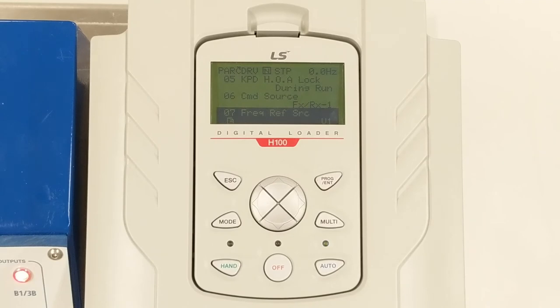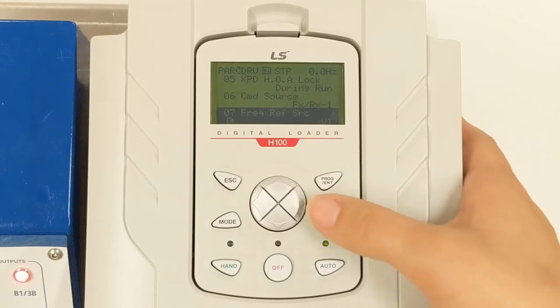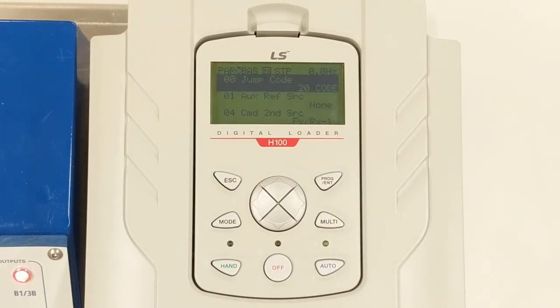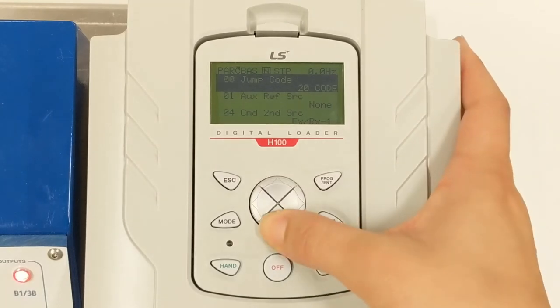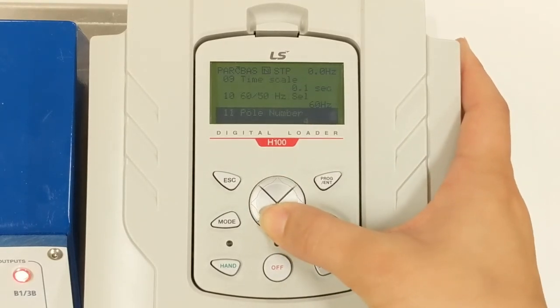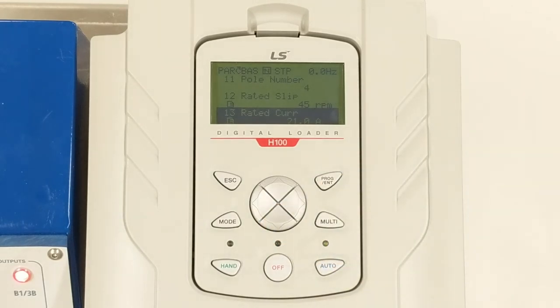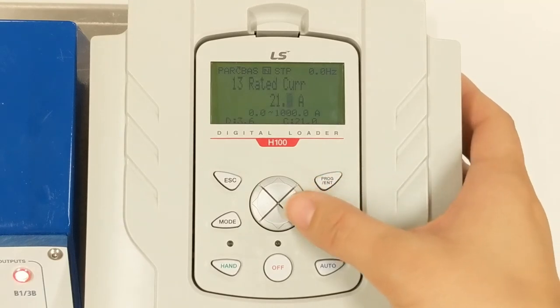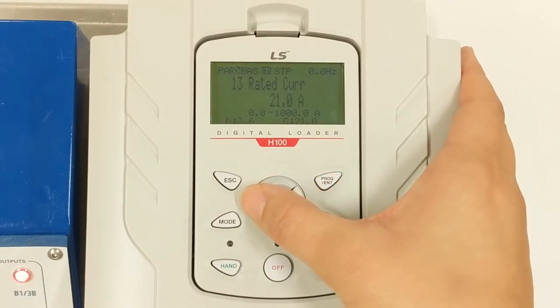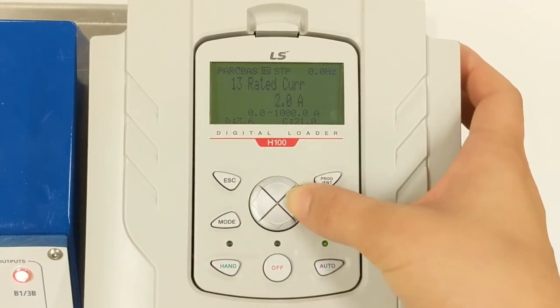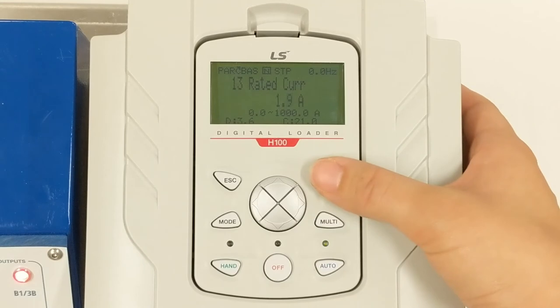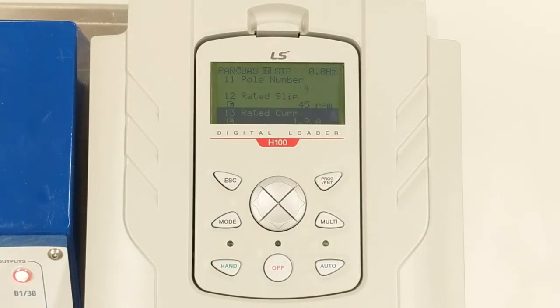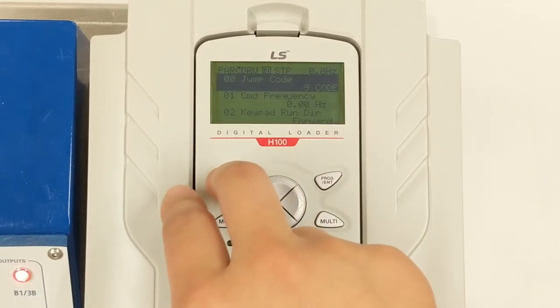Now before we check our auto operation, let's check another important parameter. Press the right arrow to go to the BAS group. BAS stands for basic parameters. Press down until you get to setting 13, rated current. This is where you need to set the motor's full load amps based on the motor nameplate data. Our motor here is 1.9 amps at 230 volts. Press the program and enter key and use the arrows to adjust the setting to your motor FLA. Then press the enter key once you have it set. This setting is important as it sets the overload level to protect your application and the motor itself. Press the escape key a few times to go back to the main monitor display.